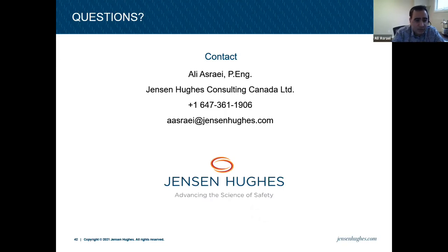I think you can ask the engineer. I don't know a best way of doing that other than some training for FPOs. I believe Chris is doing that to some extent. Maybe Chris, you can comment on that, but as long as you get training that you understand these measures and what you should be looking for, what you want to see is how they justify that the system is working properly, right? If you see the steps that they took, they looked at the system, they did an assessment, they say the building code is asking for this, the system was installed based on this, we did a test, it's performing based on this. These are the things that you need to see. If they just say, we confirm in two sentences that the system is working, I wouldn't accept that. They need to do an assessment, right? I think you can tell when you're looking at the document whether someone did an assessment or just went into the building and said the system is good.